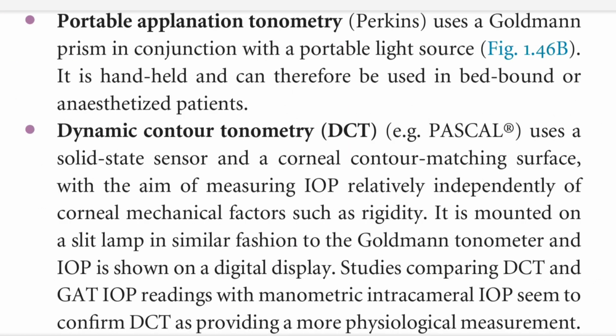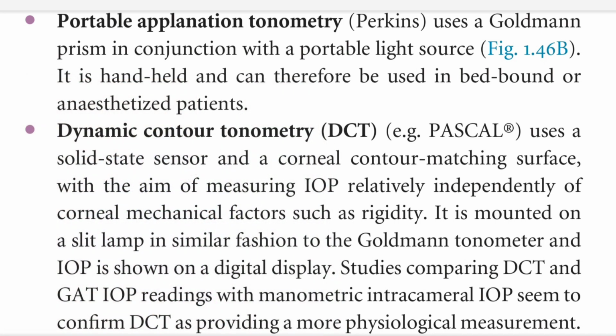Portable applanation tonometry. Perkins uses a Goldmann prism in conjunction with a portable light source, figure 1.46b. It is handheld and can therefore be used in bed-bound or anesthetized patients. Dynamic contour tonometry, DCT, for example Pascal, uses a solid-state sensor and a corneal contour matching surface, with the aim of measuring IOP relatively independently of corneal mechanical factors such as rigidity. It is mounted on a slit lamp in similar fashion to the Goldmann tonometer and IOP is shown on a digital display.